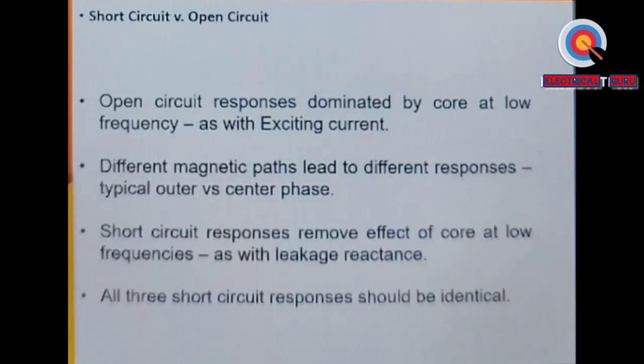Open circuit response is dominated by the core at low frequency. As with exciting currents, different magnetic paths lead to different responses, typically outer versus central phase. Now here I would like to draw your attention that the outer phases, that is R and B, are on the outer side of the core. So it does not have a closed loop magnetic path on the other side. Whereas Y phase has a closed loop magnetic path both on R and B side, so its behavior can be slightly different.